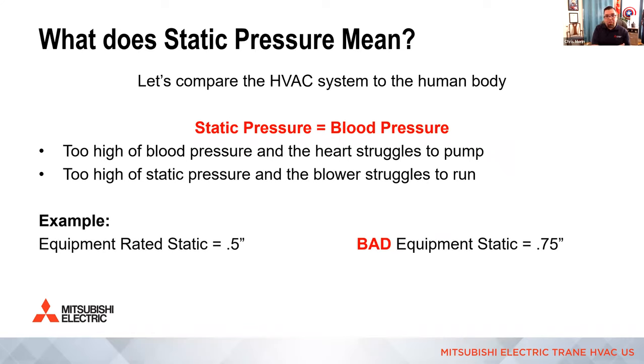So as an example, if it's rated for 0.5 or the design was 0.5, but we're running at 0.75 total, we have a problem, right? And when we start the system up, that might say, oh, I need to turn the fan speed down to design. Or if we're out there on service, it might say maybe my coil's dirty or my secondary heat exchanger's dirty or my filter's clogged, right? Yes, we're talking about total external static pressure here. Yep.